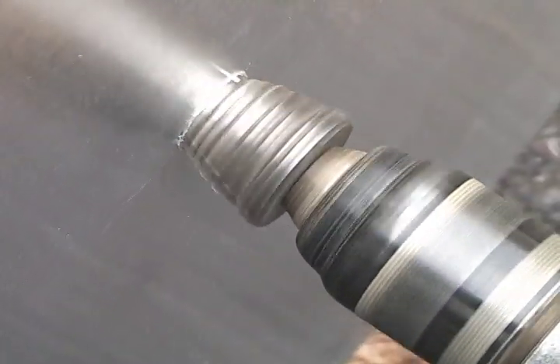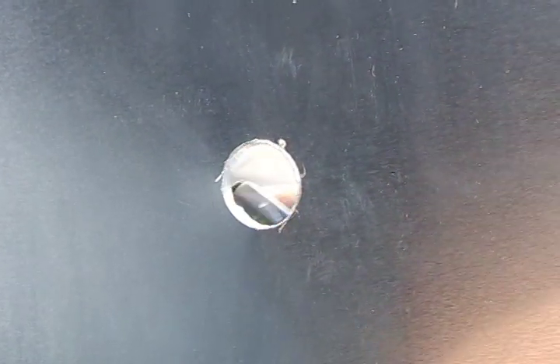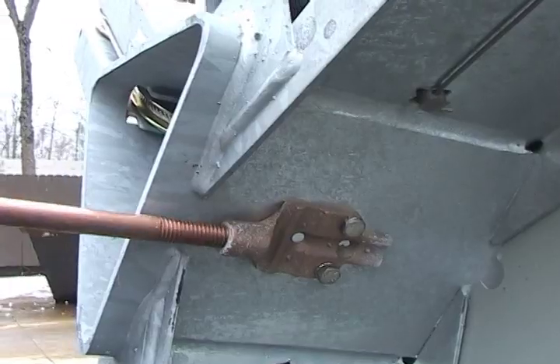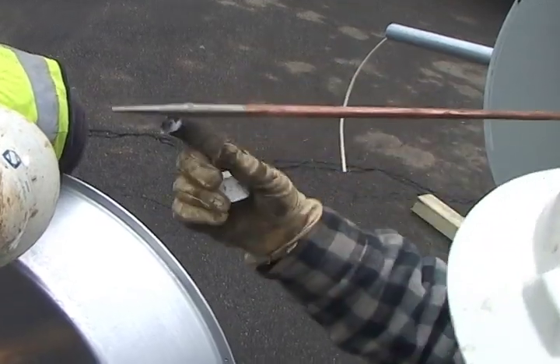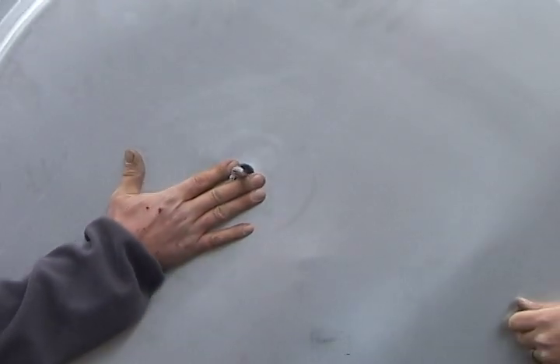If a lightning rod is used, the head frame cover has an indentation in it for the location where the rod goes through it. A 7/8 inch hole needs to be drilled and deburred at the position of this indentation. A rubber grommet is supplied to insert into the new opening. The rod is then screwed into its mounting bracket. Put some lubricant on the grommet and rod for a smooth installation. Install the head frame cover onto the head frame and secure it with the screws and lock nuts provided.